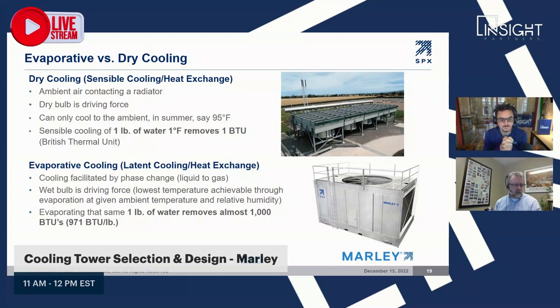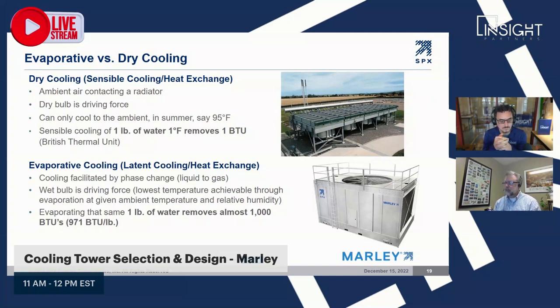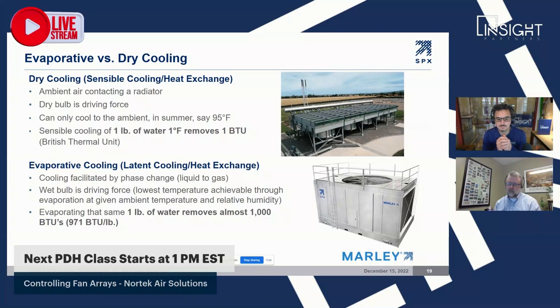The November 2022 ASHRAE Journal featured an article by Ken Mortensen of SPX Cooling Technologies — also the president of the Cooling Technology Institute — on evaporative cooling's efficiency value and actual water savings, which is counterintuitive to most people. Using data from the U.S. Energy Information Administration (April 2021), the article shows that a dry cooler takes a lot more energy, and depending on where that energy comes from, you may actually have higher water usage at the power plant. Renewable energy was only at 12% of the U.S. grid as of 2020, so power plants are still consuming significant water.